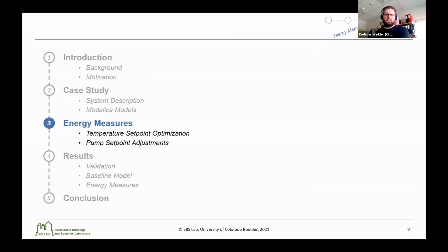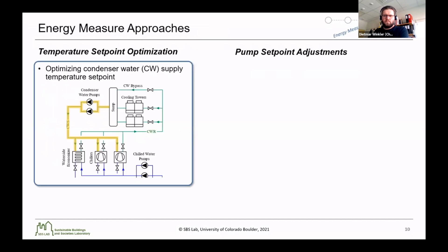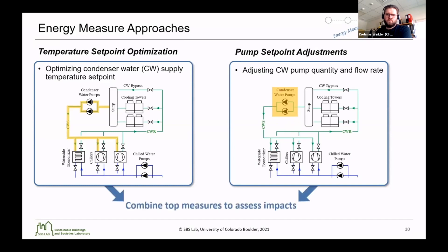With that case study, we studied a variety of different energy efficiency measures. The two main categories are a control temperature setpoint optimization and a pump setpoint adjustment. For the setpoint optimization, we looked particularly at optimizing the condenser water supply temperature setpoint — the condenser water supplied to the water-side economizer and the chillers. For the pump setpoint adjustment, we looked at adjusting the condenser water pump quantity and flow rate. We also looked to combine the top measures from each category in order to assess the combined impacts.